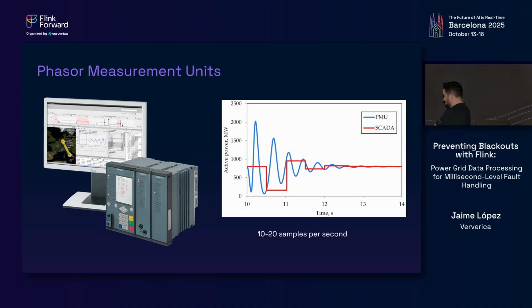If you see here on the chart on the right, the time resolution of a SCADA is going to be pretty low. And the way to combat this, or to patch for it, is to add something called Phasor Measurement Units. These are high resolution time series pieces of equipment that you add to a transformer or a generator, and that can give you that high resolution time series data.